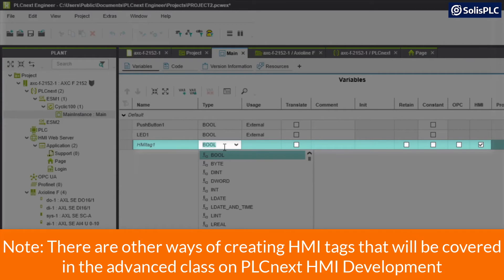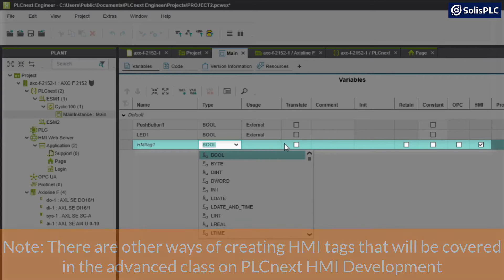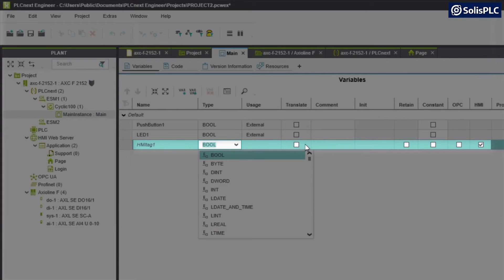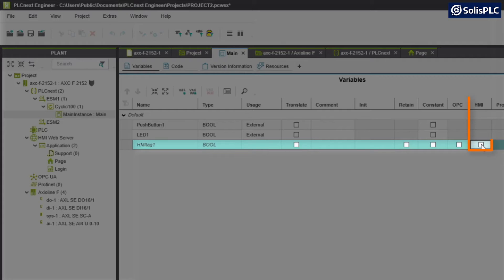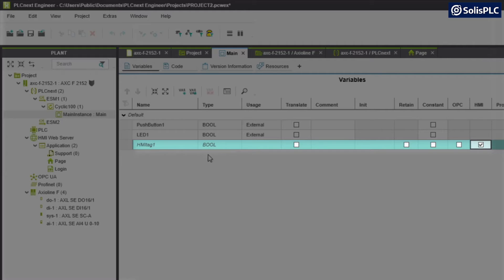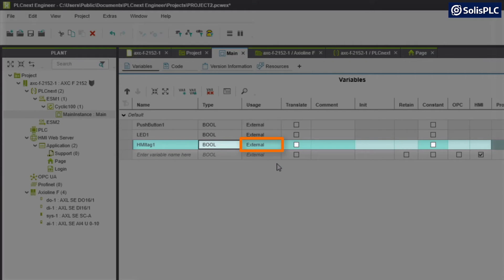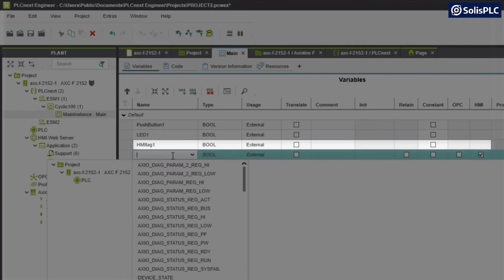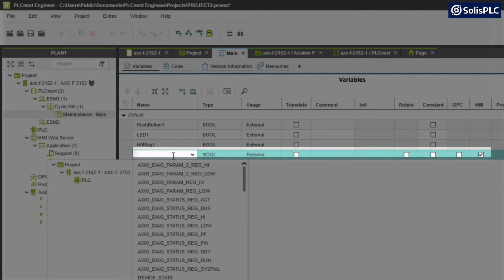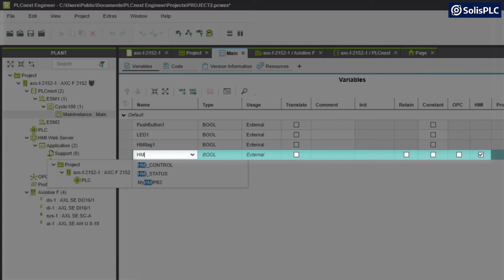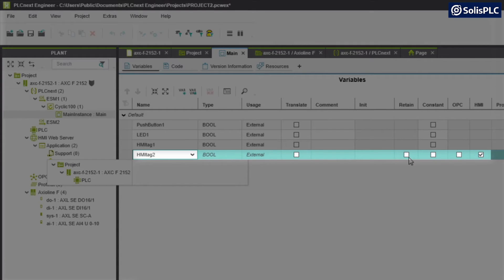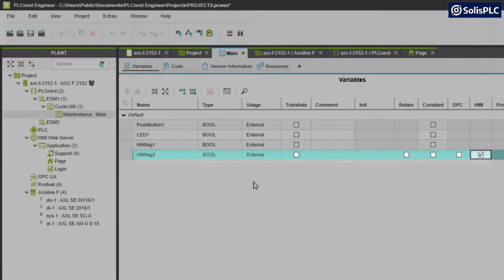Here I'm going to specify two more HMI specific tags. I'm going to give this a name, so this is going to be HMI tag 1. This is going to be of type Boolean because it will be working with a push button. What I need to check here is the HMI box near the end in this column. I'm also going to make sure that this tag is external because it's going to be accessed by an external application. I'm going to create a second one of the same type: HMI tag number 2, Boolean, external and an HMI tag.